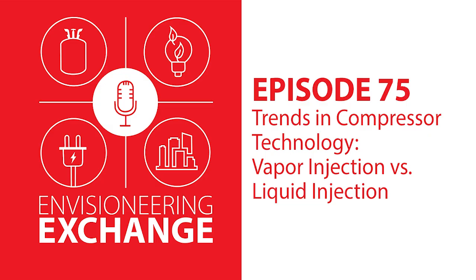Yeah, it's a bit more tricky than in previous times with a non-injection compressor, because in more simple times you had just a standard 10-term set of polynomials, and you could run the simulations based off the AHRI standards, and then, okay, here's your capacity. But with vapor injection compressors, now you have extra variables that you need to consider, like injection temperature and SDT, saturated discharge temperature, things like that. You need those inputs to characterize how the system is going to perform at these off-rating conditions. So it's a more complicated process to pick the compressor, and also to do simulations and the other individual component selections, because you're looking at a lot more operational points than you would have in the past.